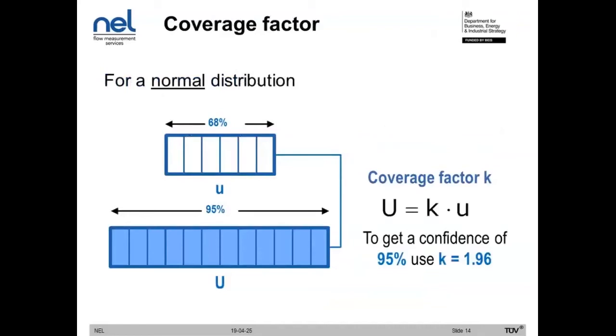To convert between a standard uncertainty and an expanded uncertainty, we need a coverage factor, which is defined here as the letter k. If you want to move between the standard uncertainty of 68% to the expanded uncertainty of 95%, you use a coverage factor of 1.96, which is sometimes rounded up to 2. We can see what the effect has been. We started with quite a small uncertainty, but a low confidence level. And now we've moved to a higher confidence level, but our uncertainty band has effectively doubled. So we have a less precise measurement, but we have greater confidence in the uncertainty.